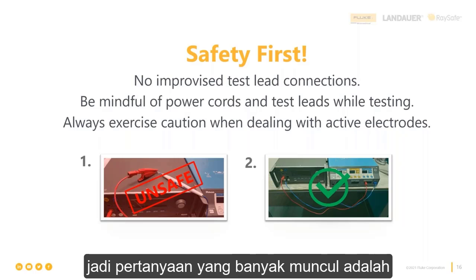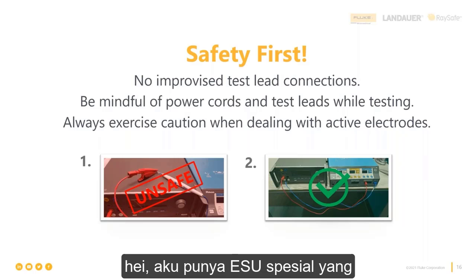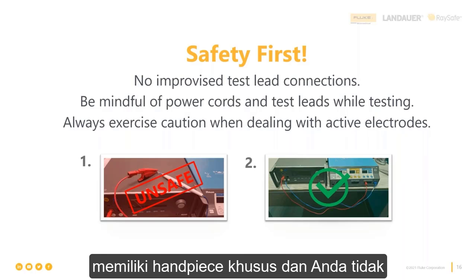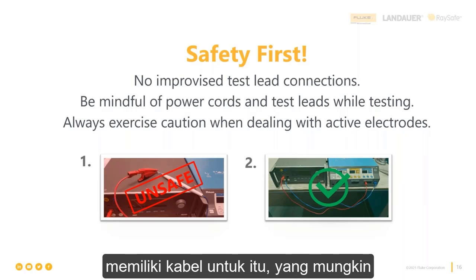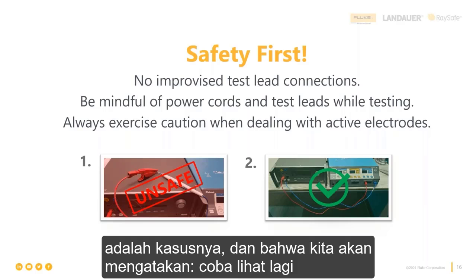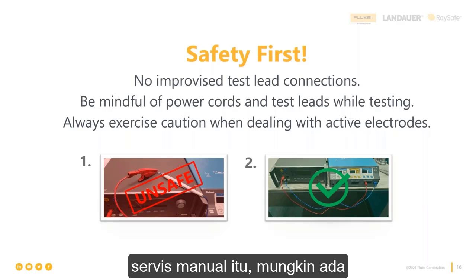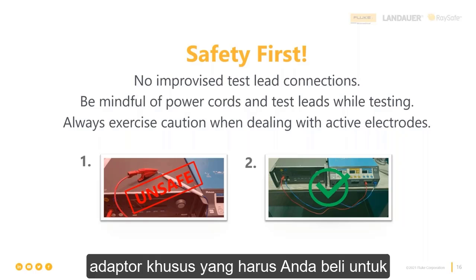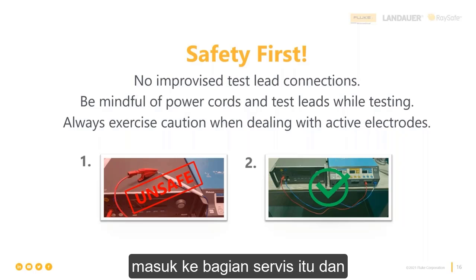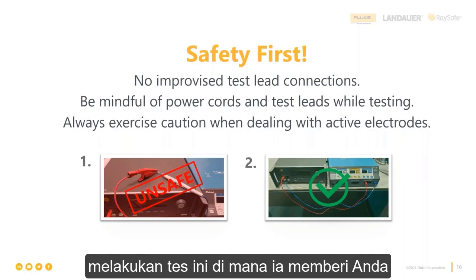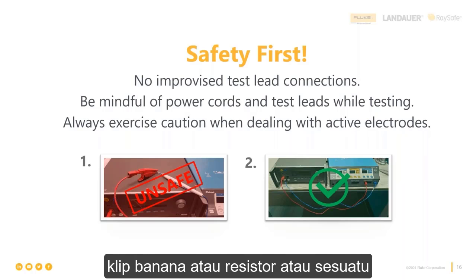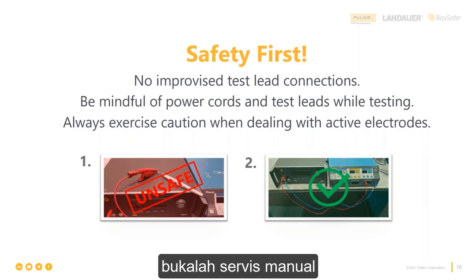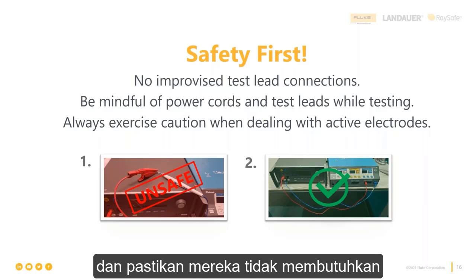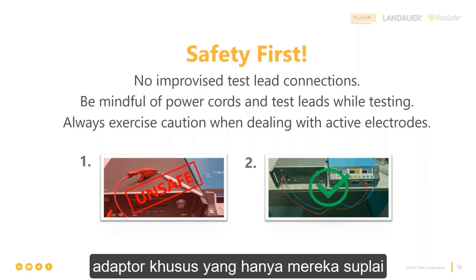So the question that comes up a lot is, hey, I have this specialty ESU that takes a special handpiece, and you don't have the cable for it. That might be the case, and with that, we're going to say go back to that service manual. There might be a special adapter you have to buy to get into that service portion and perform this test, where it gives you a banana clip or a resistor or something to allow it to get into that service mode. So again, if you can't figure it out and you have to go to that pencil tip, go back to that service manual and make sure they're not calling for a specialty adapter that they supply.